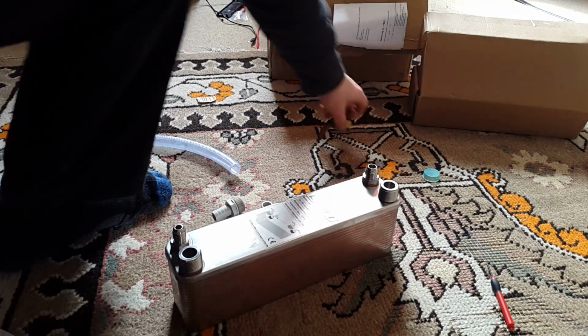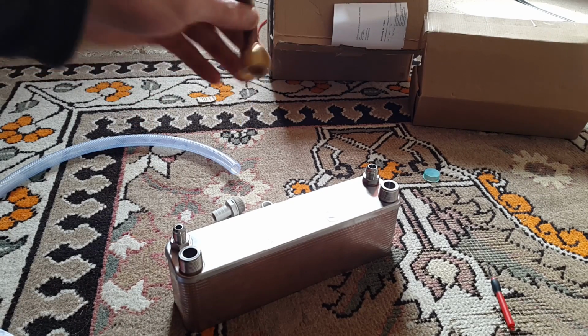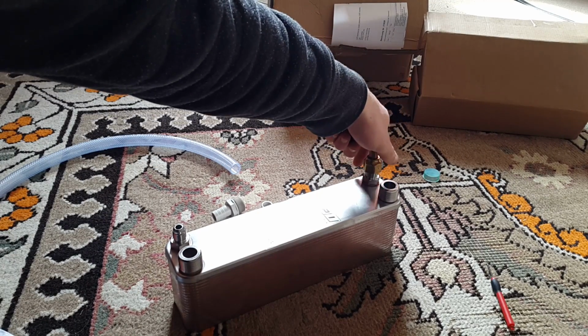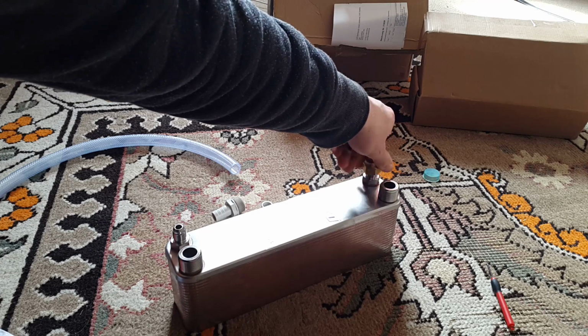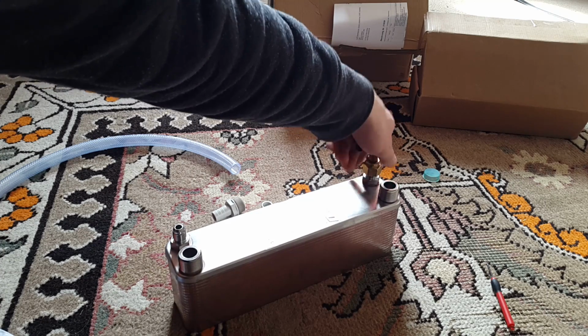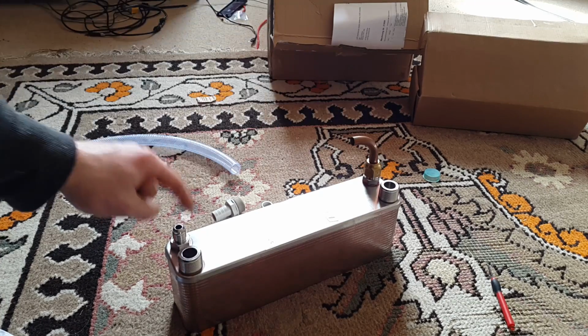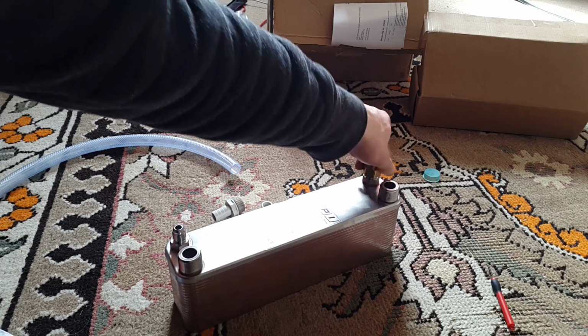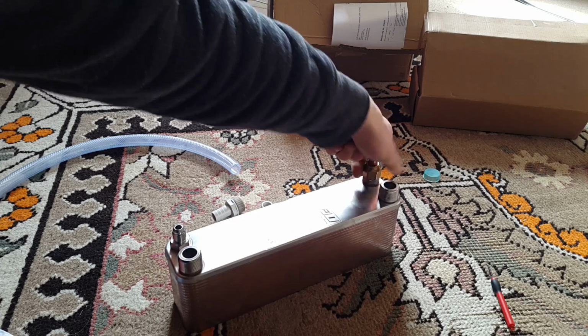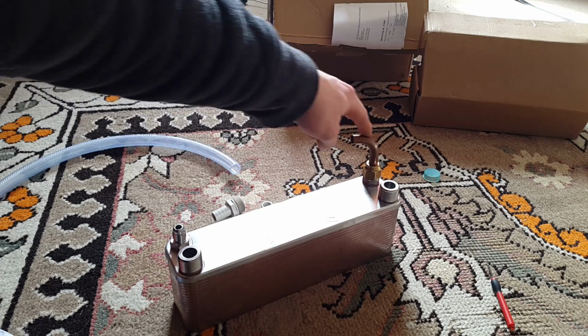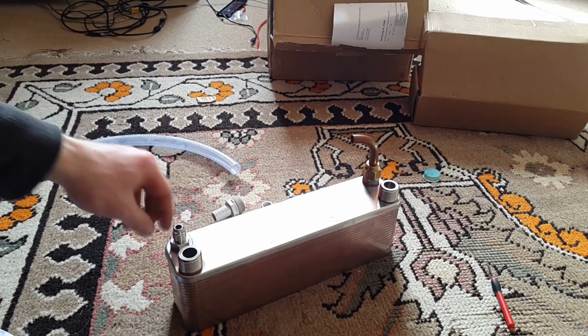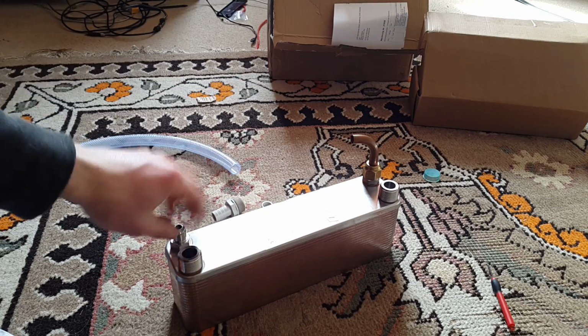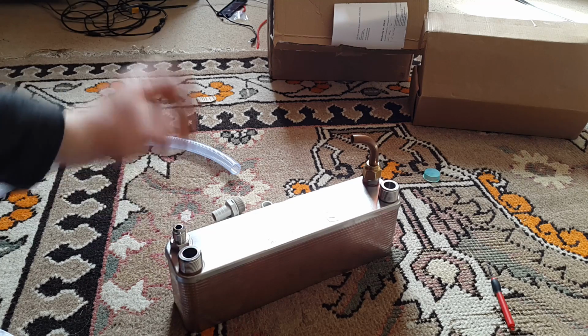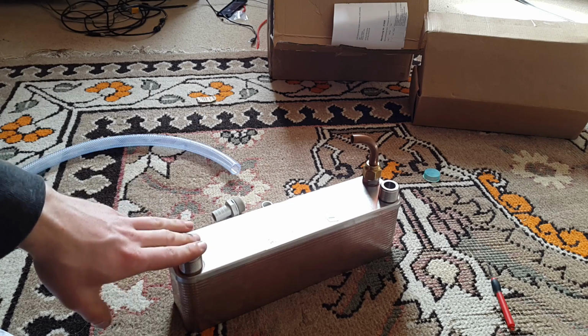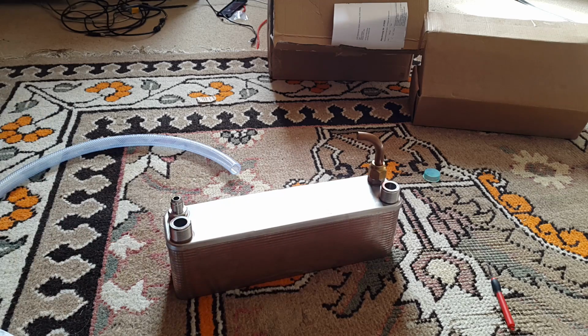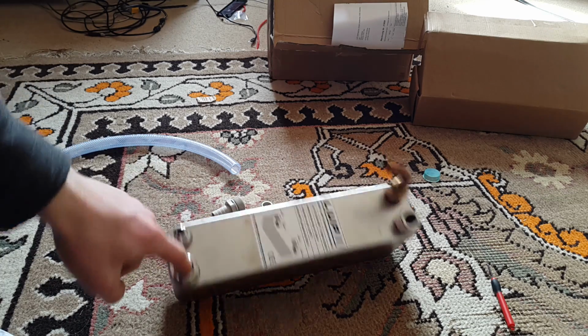I've got a flare fitting made up here, and that screws on there, but I've still not got my 3/8 copper tubing yet. I'm waiting for that so I can make up the other flare fitting that goes on this end, which is smaller. I reckon the hot gas out the compressor should go in the larger fitting, then come out the bottom through the smaller one, through my sight glass, and then onto the filter dryer from there.